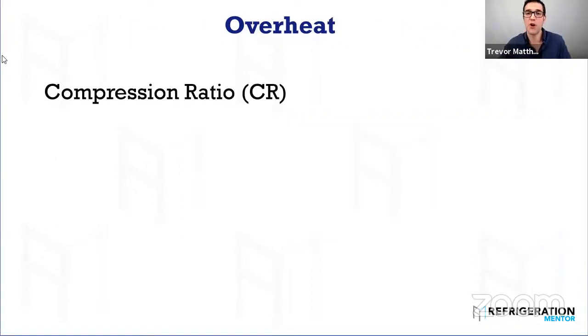Okay, compression ratio. You see, I get pretty excited talking about this stuff. I could go for a long time, so maybe I'll have to get a warning from Vanessa. Compression ratio is so important to understand. As a technician, I never even thought of compression ratio. I learned about it in school, but it's so important, because if you have a high compression ratio, the compressor's working harder, it's gaining more heat, and it's causing issues in your system. It's system related issues or design that cause high compression ratio.